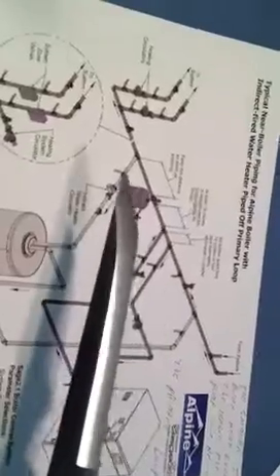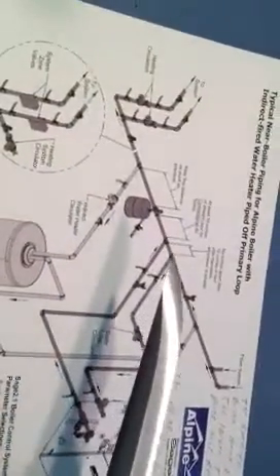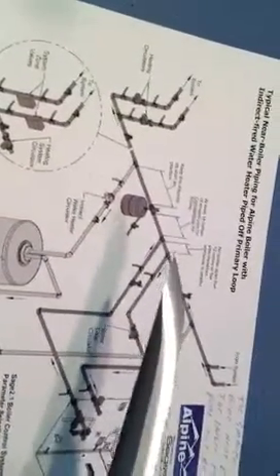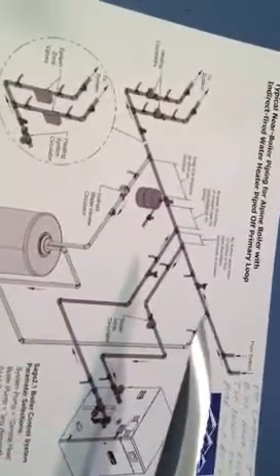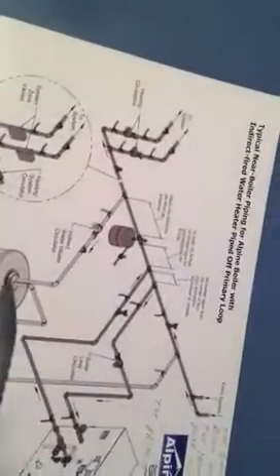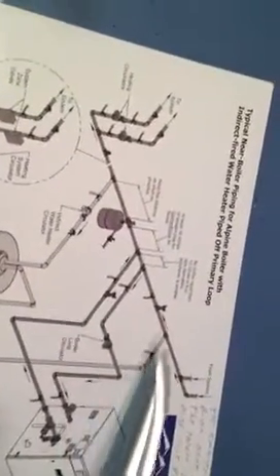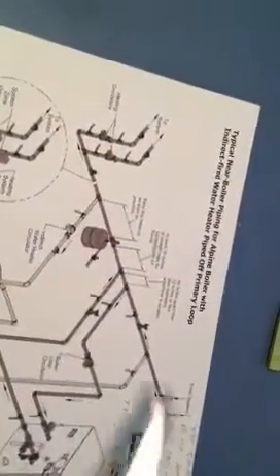But it's nothing more than a simple T into the water line with a circulator pushing into the storage tank and then back out of the storage tank following the gray line up and the return. Now don't forget one T is on one side of the closely spaced T's, the other tie-in is on the opposite side. So you have your circulation in the tank and out of the tank back to the main pipe. This being your circulator for the indirect hot water heater, and of course your hot and cold to your shower isn't shown.